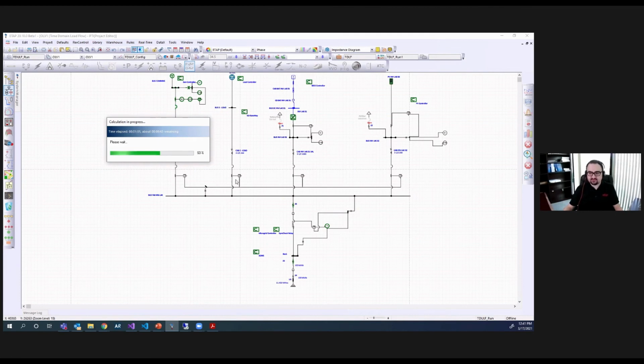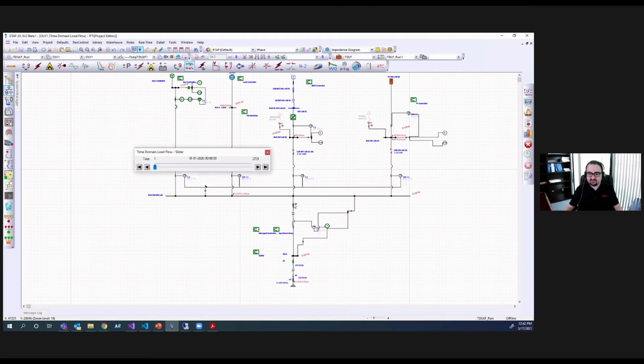based on the logic, try to increase the state of charge of the battery to enable it to support the system during the islanded operation. And if needed, it will shed the load or ramp up the diesel generator if we need more source, or if we don't have enough source, it will shed the load. And also right before the system goes to planned islanding, it will try to decrease the exchange of active and reactive power at point of interconnection, making the system ready to go to islanded operation. As a result, if the system goes to islanded mode, the system sees less stress and will remain stable.